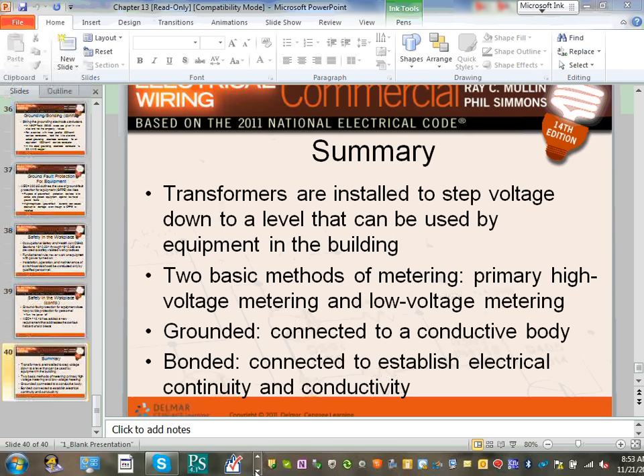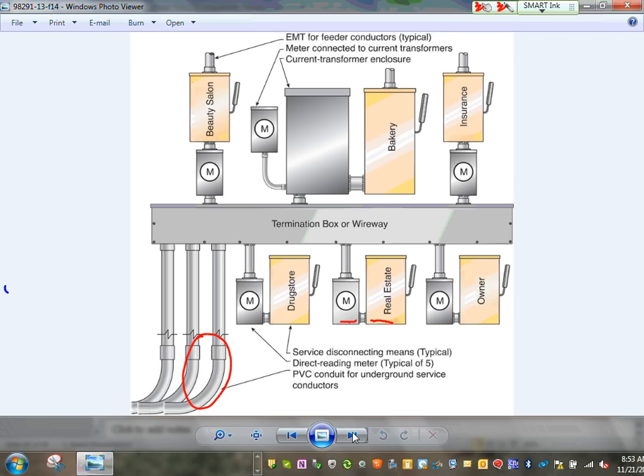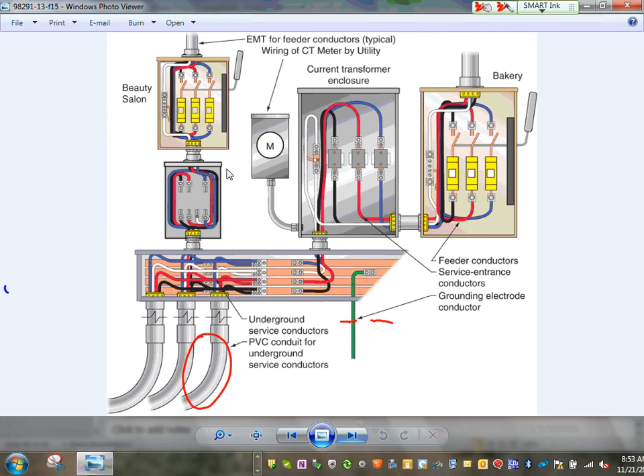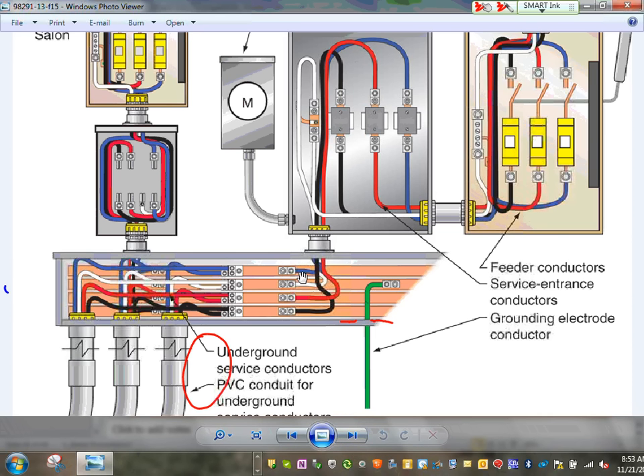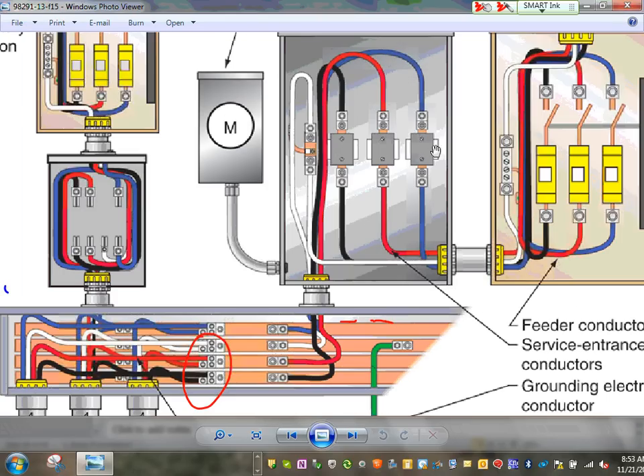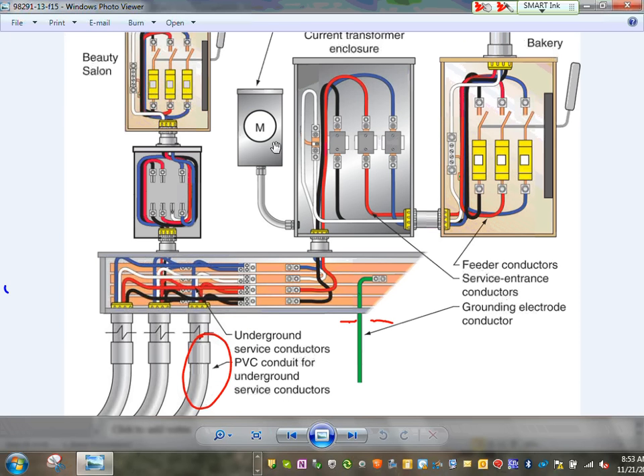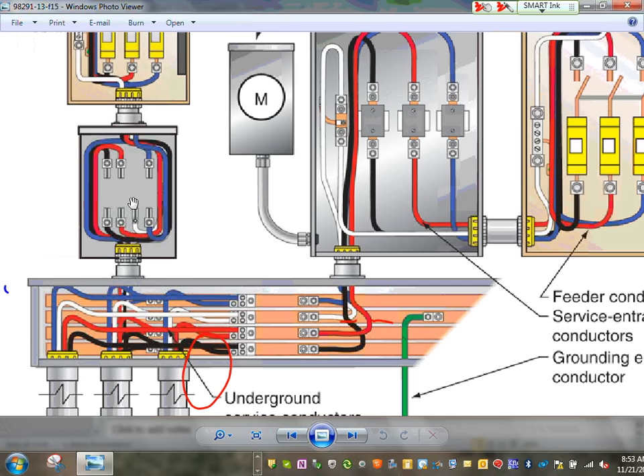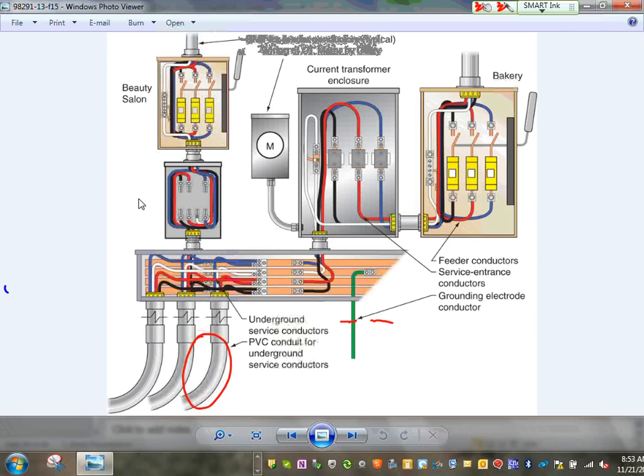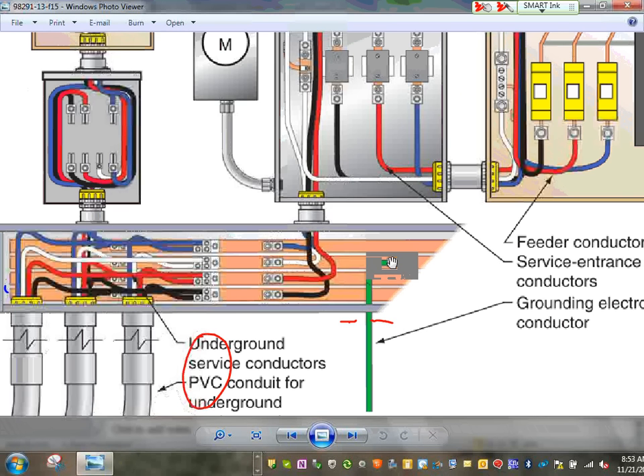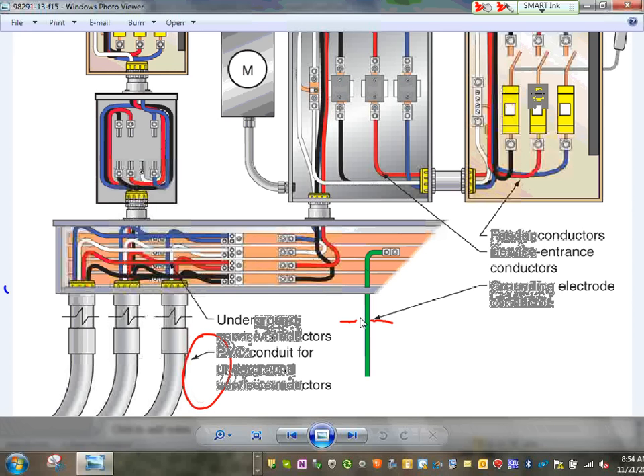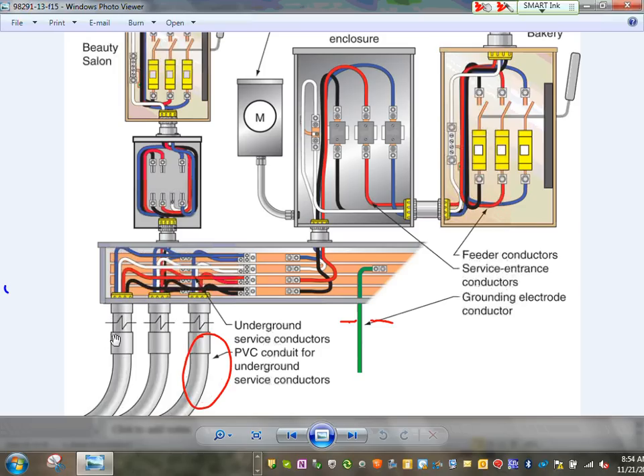Let me see if I can have a couple of other pictures to share with you. We talked about these. Here's a typical wiring diagram, guys. You bring the neutral here. Adam, can you see these CTs right here? These CTs take the current and convert it to 5 amps, which is measured by that meter. You use them on anything higher than 200 amp. If it's 200 amp or less, here's how they do it. They bring the power right into the equipment. Look how they ground the neutral, the grounding electrode conductor, guys. Come right here on the service equipment and they ground it directly. Take it to the grounding electrode conductor based on the conductors coming into this conduit.